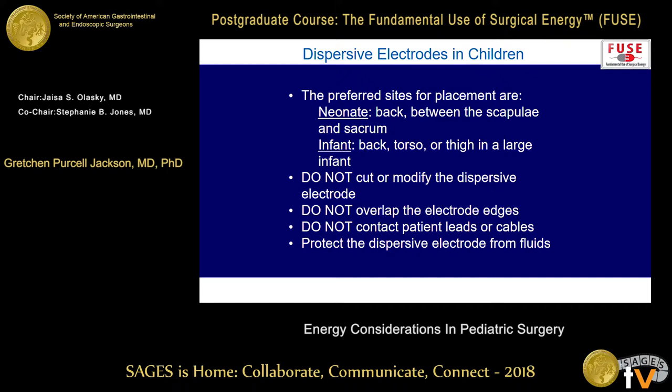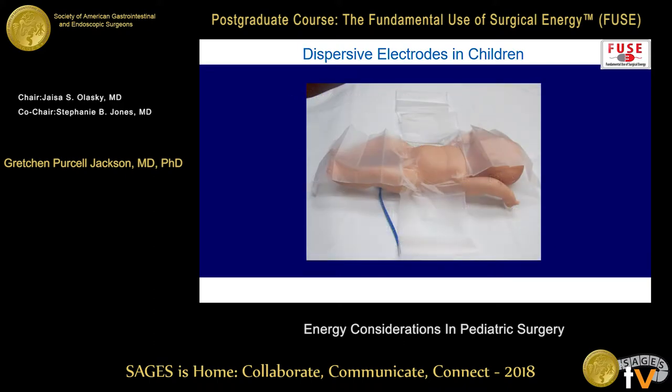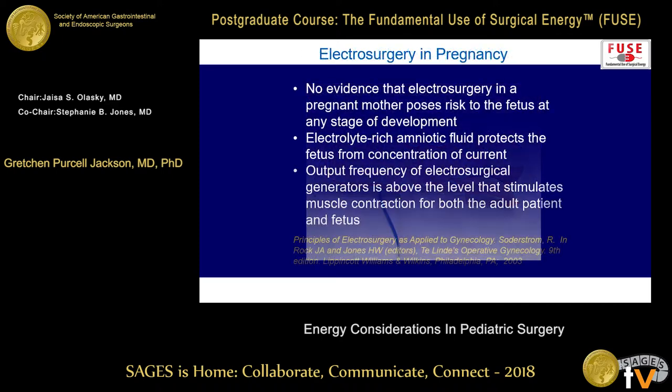In neonates, place the dispersive electrode on the back between the scapula and the sacrum. In older infants, the back, torso, or thigh can be used. Be careful with the adhesive on delicate skin — especially in newborns or premature infants where skin is thin and undeveloped — as removing the electrode can peel skin off. Fluids from the operative site or irrigation can compromise the electrode; I protect the dispersive electrode site with water-resistant drapes. If you cannot get a dispersive electrode to work, bipolar devices are always your alternative.